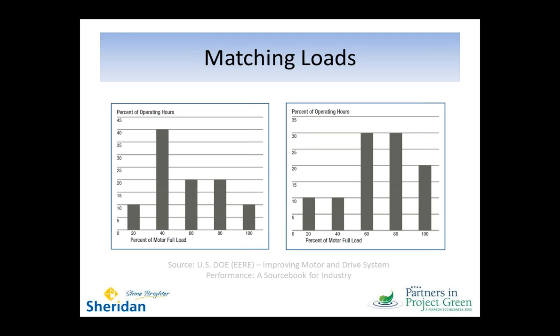Now looking at these two different graphs here, they look roughly the same. On the surface, we've got a varying profile of different operating hours at different motor speeds and loads. In the left-hand graph, we see that the motor spends a fair bit of time at about 40% load, and then it spreads its time over the remaining loadings. This might be the application where you've got a variable speed drive. So in this case, at 100%, the motor's perfectly happy. You scale it down in speed to where it's on 40% load, and it's perfectly happy with that as well. And you're covering the whole range of requirements of the motor in the system.